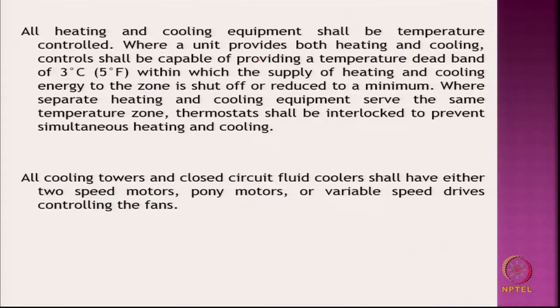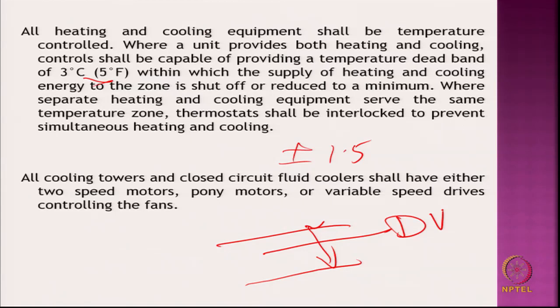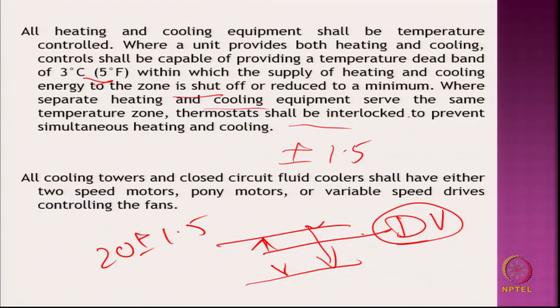So, there should be temperature control, both cooling and heating, plus minus 1.5 degrees, as I was saying, so plus minus 1.5 will make it a 3 degree band. This is what we call the desired value, the design value. Supposing I want to maintain this room at a design value of 25 degrees centigrade, let us say. In some cases, depending upon the situation, because our people in a tropical climate can tolerate somewhat higher temperature than somebody from subtropical areas, it might be 20 degrees, and the design value would be 20 plus minus 1.5, which means this band is 3. So it should operate within 3 degrees.